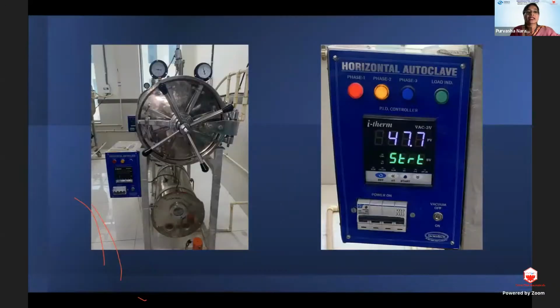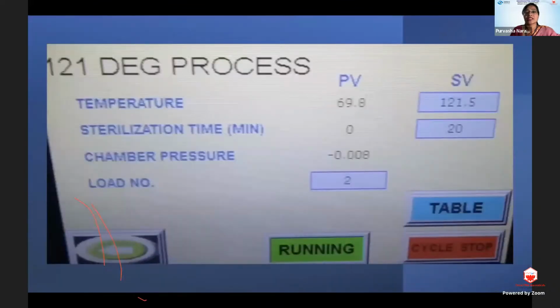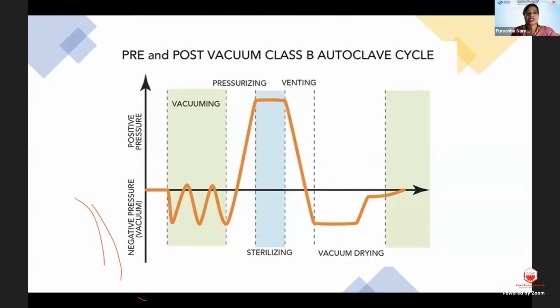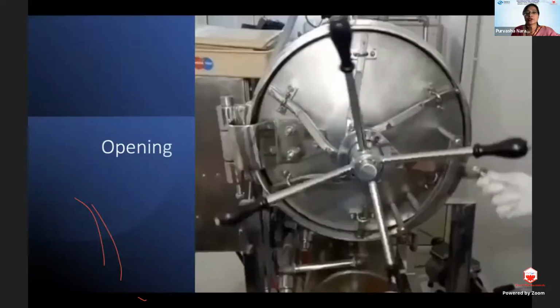And then the lid is closed and sealed properly, and the temperature is set to 121 degrees, 20 psi for 20 to 30 minutes. And this is the way to start your steam sterilization process. So this one is a pre-vacuum. This one will have 3 cycles of pre-vacuum along with the holding time, and then the post-vacuum and drying cycle is present. So almost an hour of this process takes place.